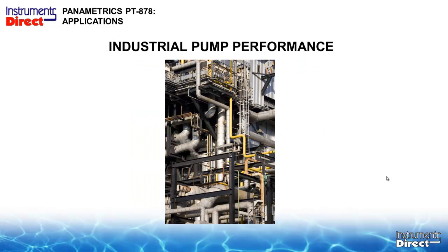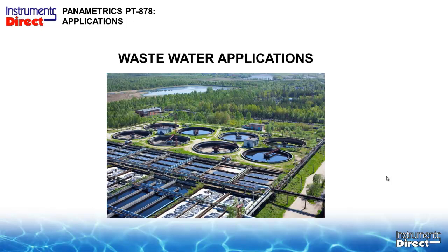the whole purpose of monitoring flow for the most part is going to be for pump performance. So regardless of your environment, that's really pretty much what the technology is used for. We've got a full pipe of liquid and we're monitoring it, and you can have a tight situation like you see there before, or you can have lots of straight run of pipe. And then the process liquid itself will vary, everything from a clean liquid to a wastewater application.